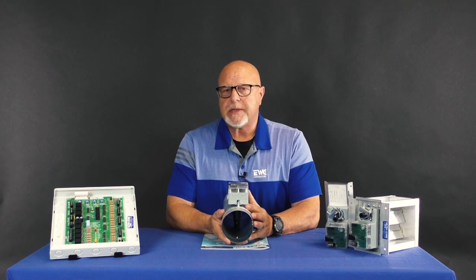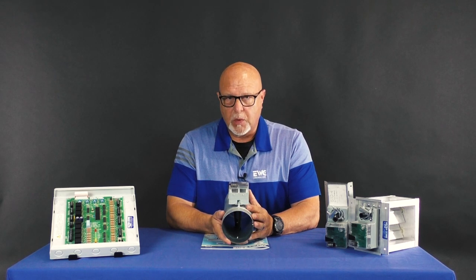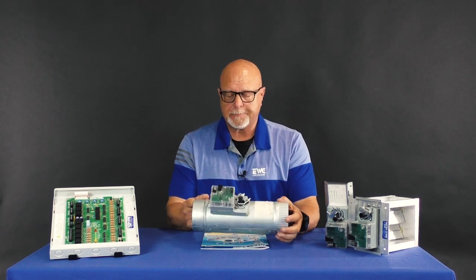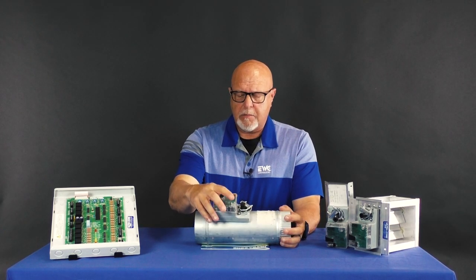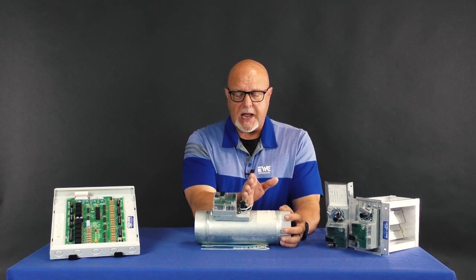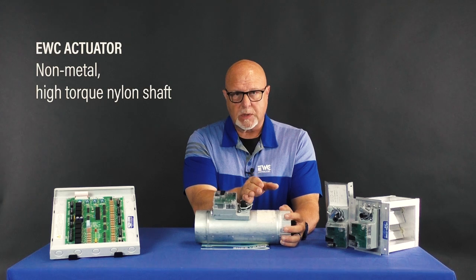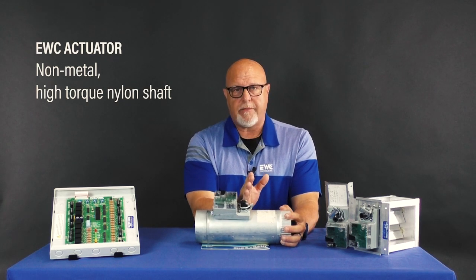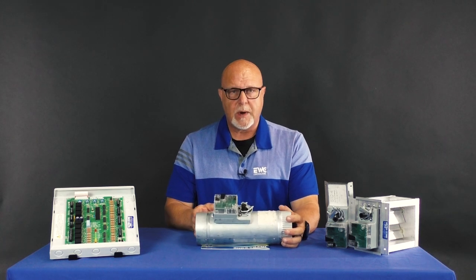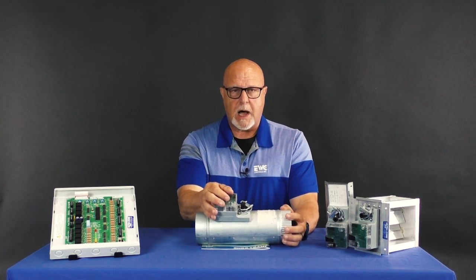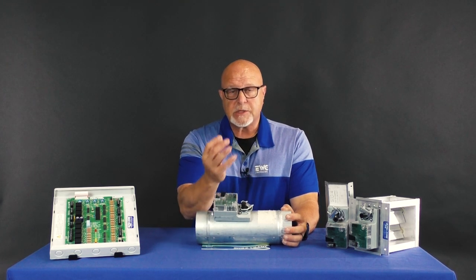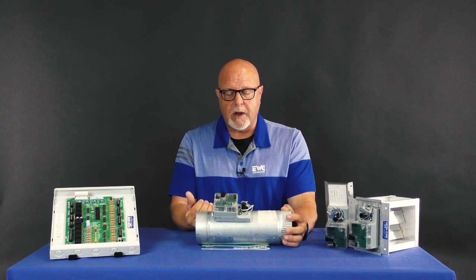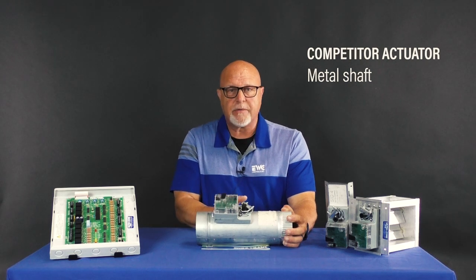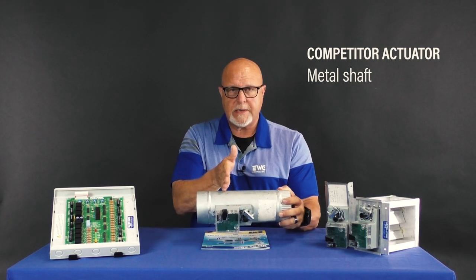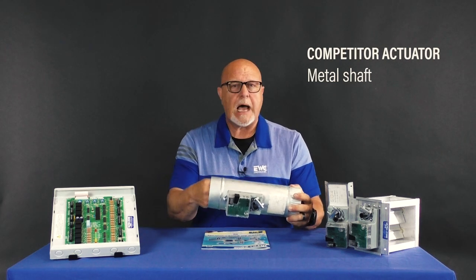One of the other features that a lot of people don't realize is so important, and this goes to the longevity of our dampers. If you notice, we have a motor actuator and a shaft that is non-metal. It is high torque nylon, exterior of the motor shaft. Most of my competition out there with the 2-wire spring return dampers have a small hot metal motor. And believe me, it gets hot. If you have ever opened up a ceiling tile and exposed a 2-wire damper, you can actually feel the heat coming off of it. Well, that hot metal motor has a metal shaft coming out of the bottom of that motor going down into the shell, or the inside of the damper.